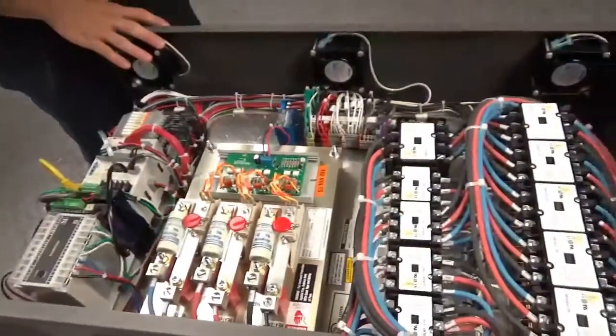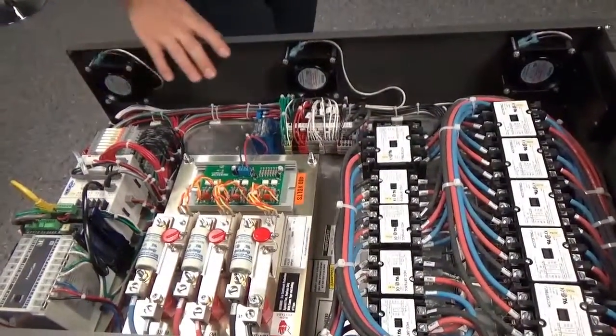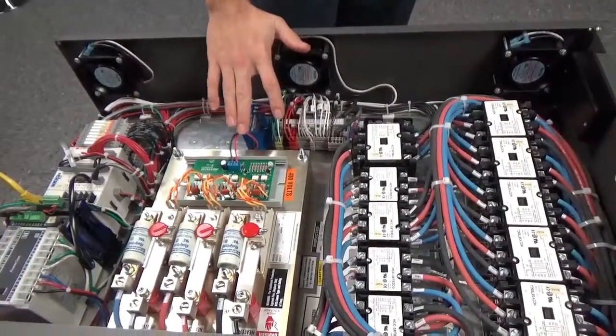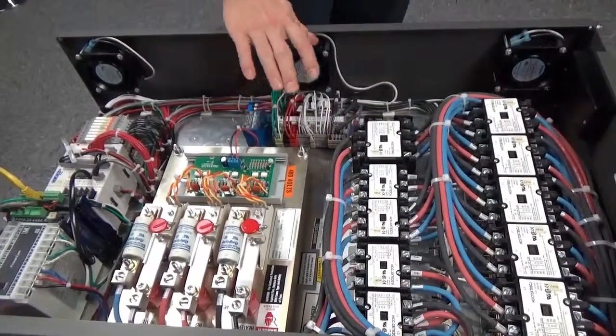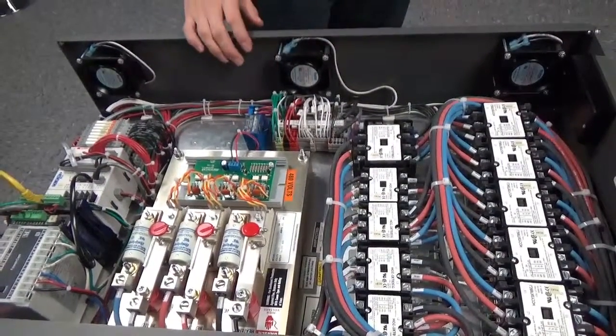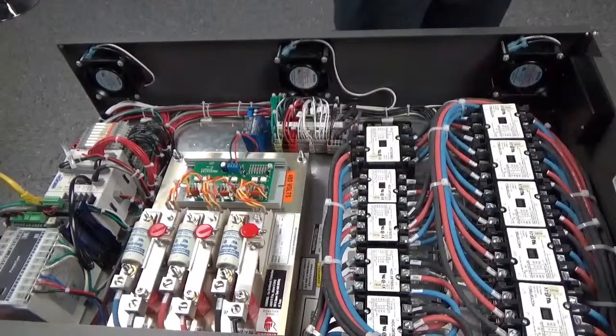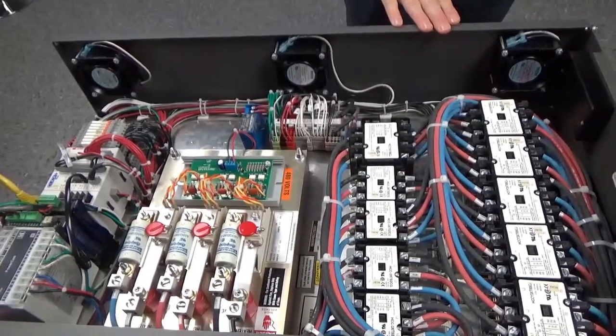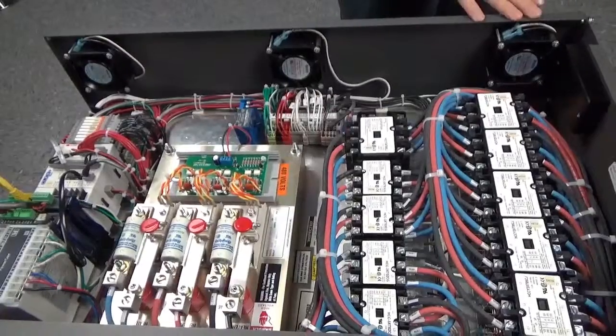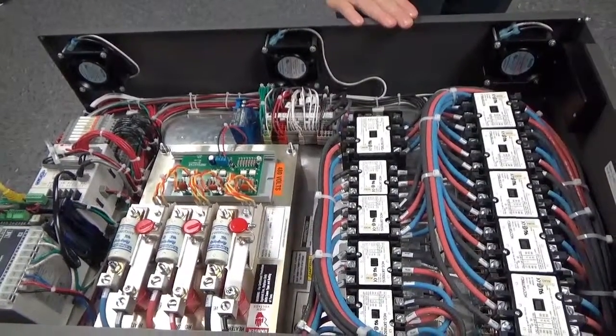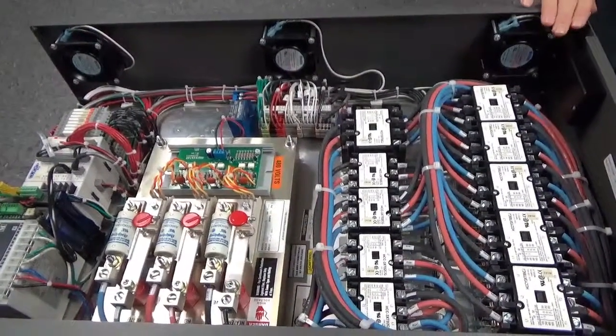This is a 200 kilowatt load bank. It is equipped with a SCR, which allows us to have infinite possibilities between 0 and 200 kilowatts. This load bank is capable of controlling 208 volts all the way up to 480 volts, 3-phase and single phase.